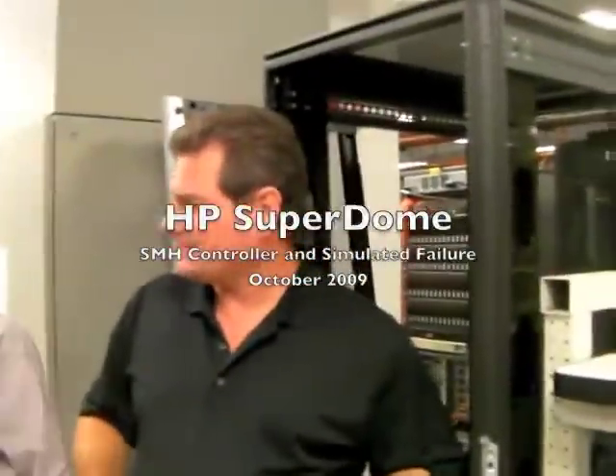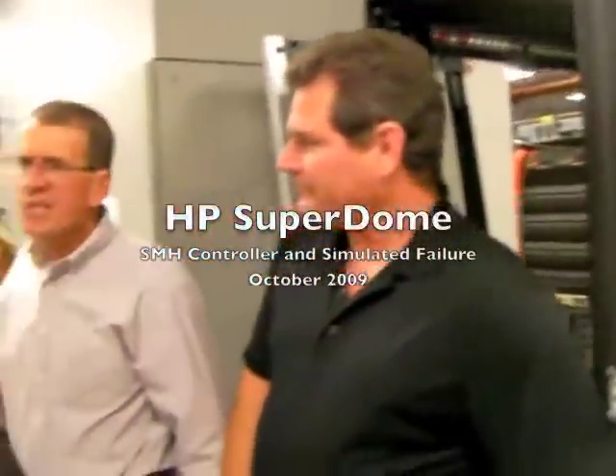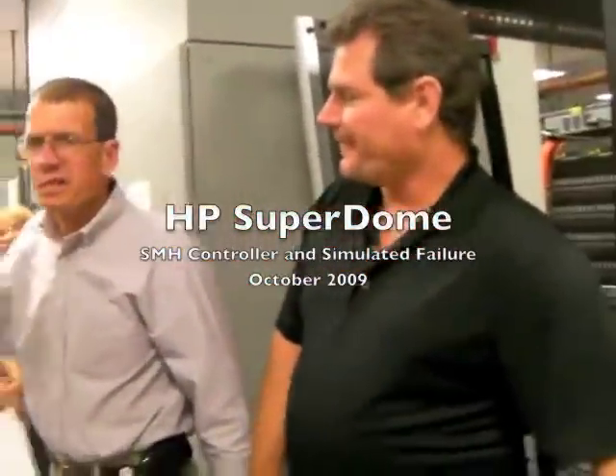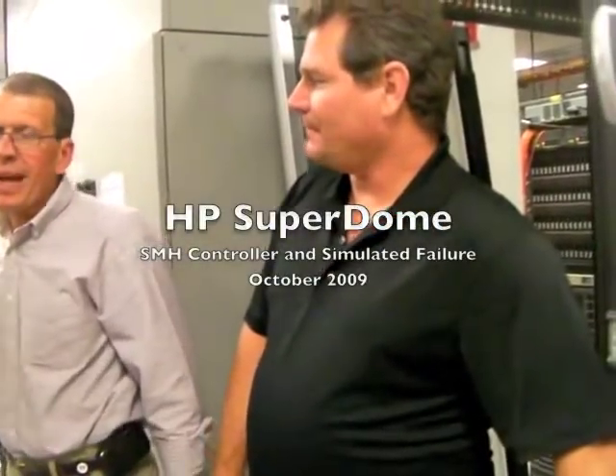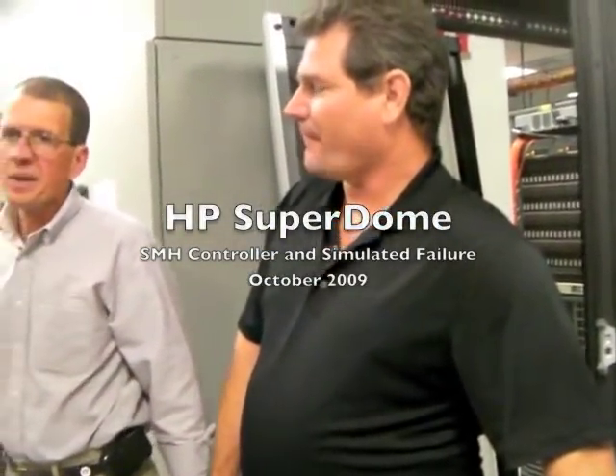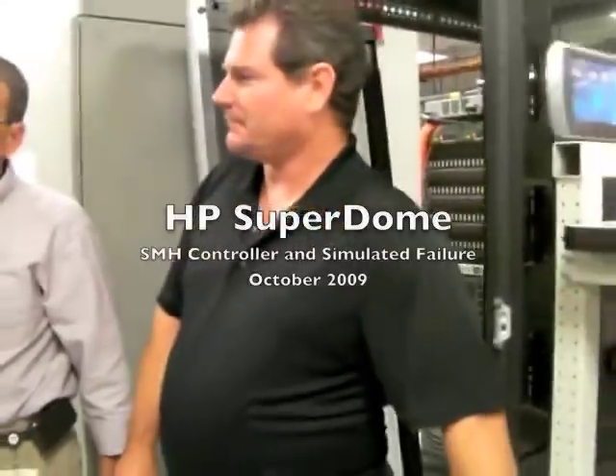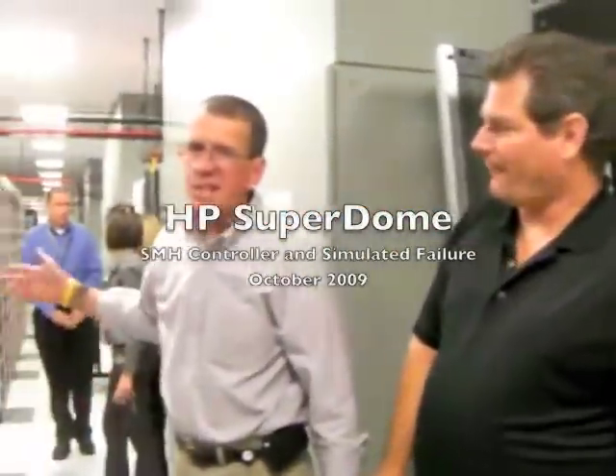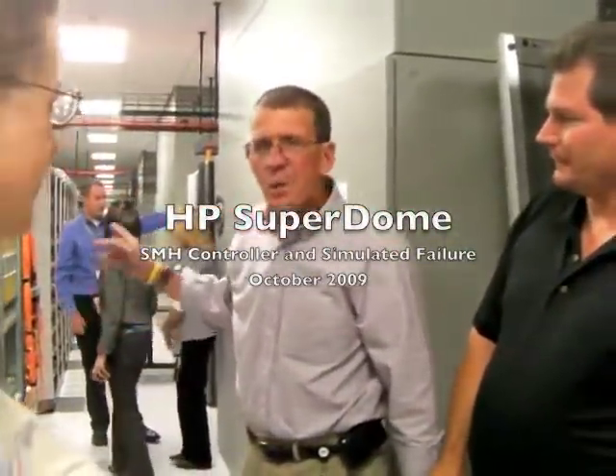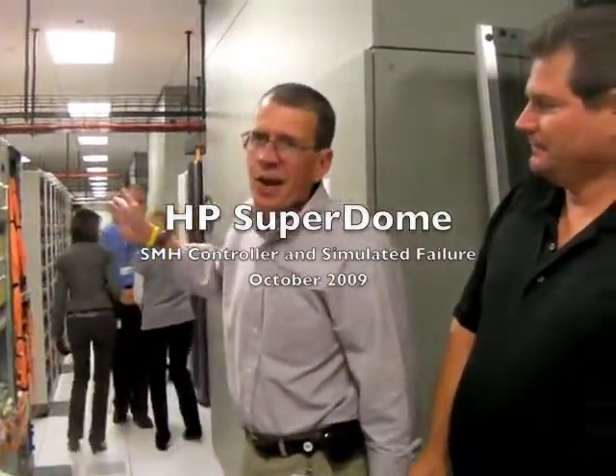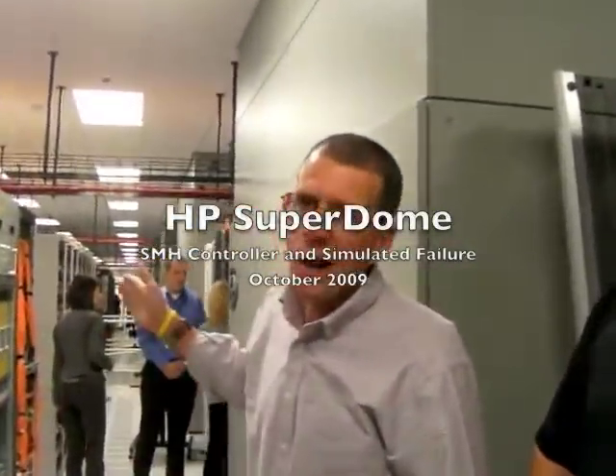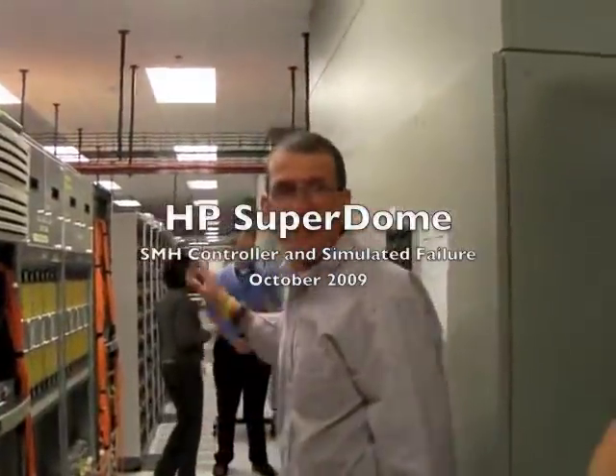Mark mentioned that the power and cooling are redundant. So what I'm going to do is simulate a blower failure just by pulling it out a little bit, and then you can see how SMH picks it up, and you can see that it doesn't cause the system to crash. Assuming that I check and make sure that I'm not showing you what happens when there's two blower failures. So I'm going to first go do that.